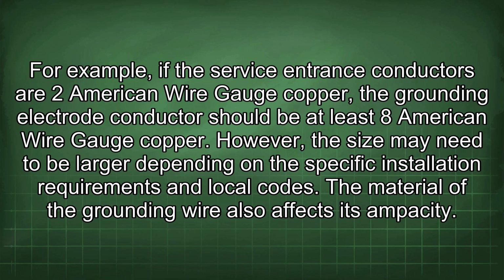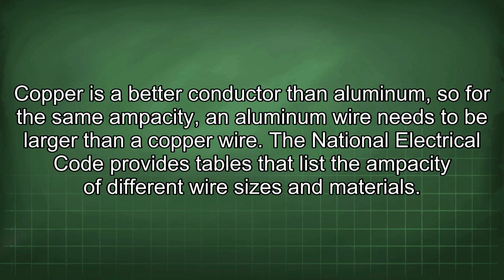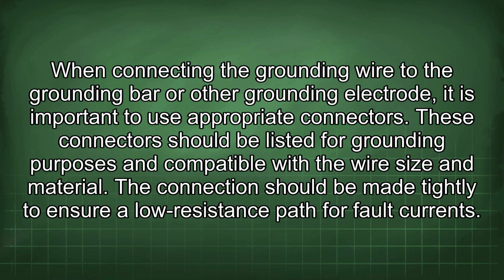The material of the grounding wire also affects its ampacity. Copper is a better conductor than aluminum, so for the same ampacity, an aluminum wire needs to be larger than a copper wire. The National Electrical Code provides tables that list the ampacity of different wire sizes and materials. When connecting the grounding wire to the grounding bar or other grounding electrode, it is important to use appropriate connectors. These connectors should be listed for grounding purposes and compatible with the wire size and material. The connection should be made tightly to ensure a low resistance path for fault currents.